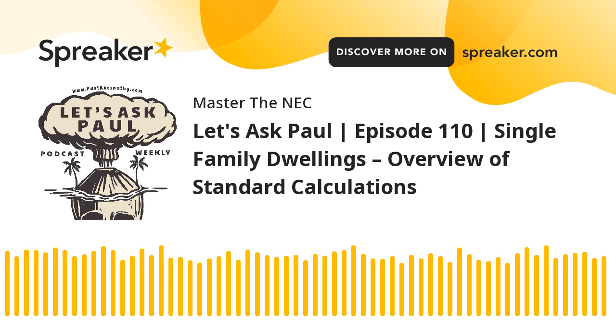Okay? So we're going to go to 75, and it looks like in order to get to 193, we're going to be at 3 aught. Or as some people say, 3 naught. That's good for 200 amperes. Right? So we would have a 200 amp overcurrent device, and we would have a 3 aught copper. And if we were doing aluminum under the 75, it looks like we would have to have a 250 kcmil aluminum. Okay, it's good for 205 amps. Okay, makes sense? Everything seems good here?